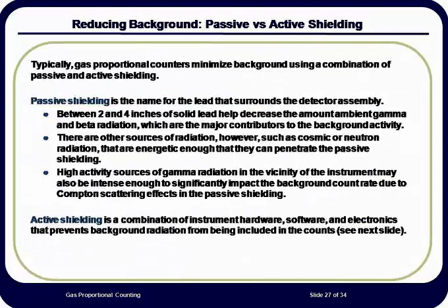Typically, gas proportional counting instruments utilize a combination of active and passive shielding to minimize background counts. Passive shielding is the lead that surrounds the detector chambers so that ambient radiation entering the chamber is minimized. However, cosmic radiation can penetrate the detector shielding and create ionizing events in the active detector area.